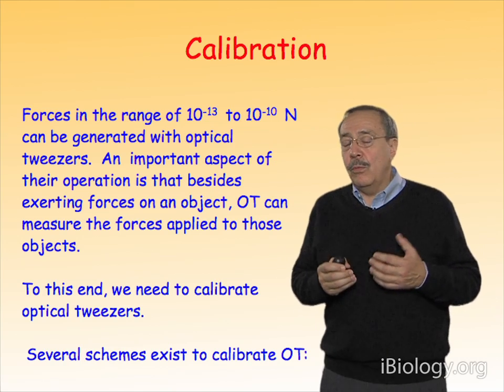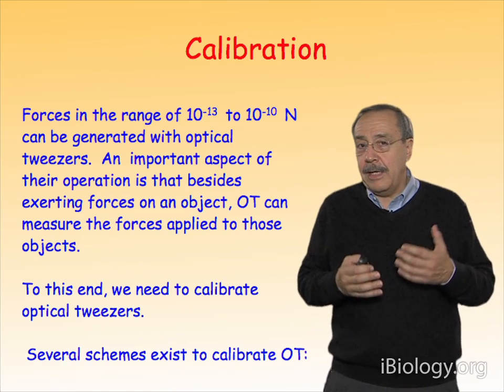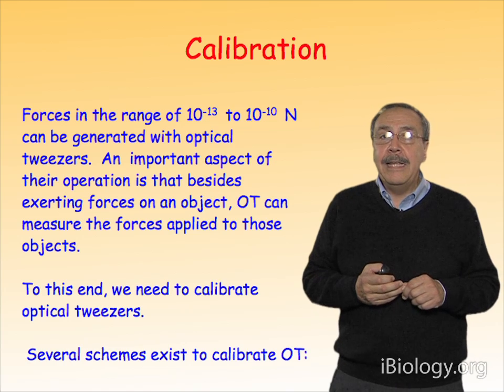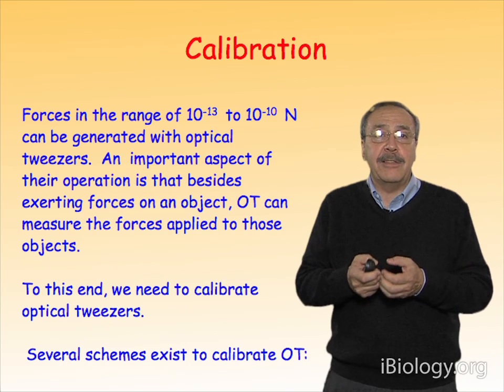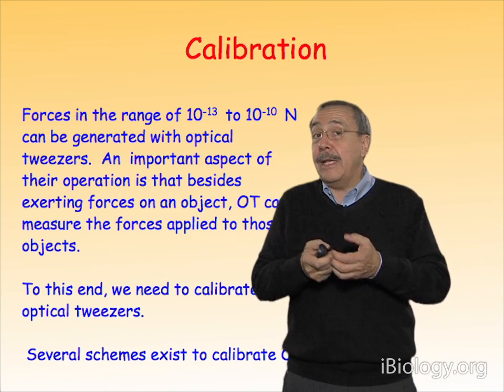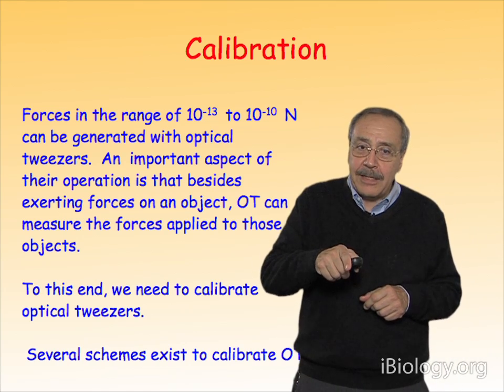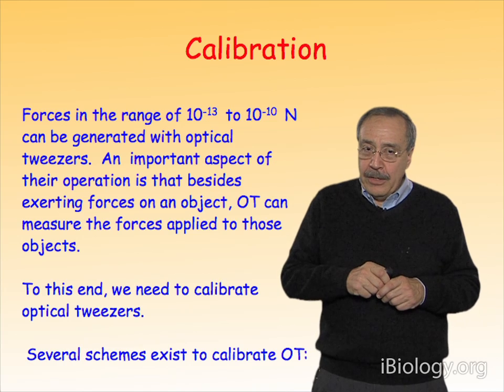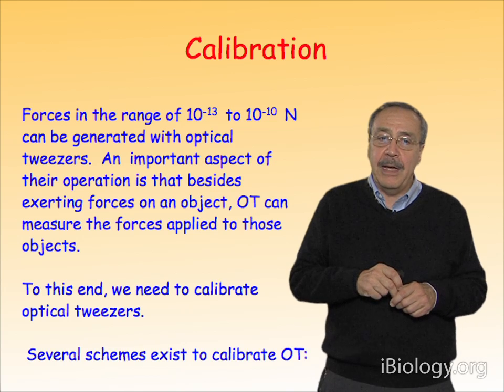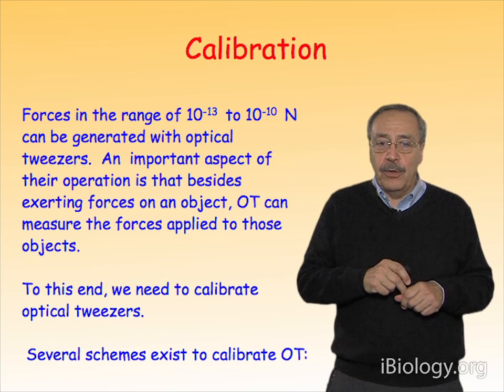One of the wonderful things about optical tweezers as a technique to manipulate and study biological processes is that they not only allow you to exert forces on molecules using the force exerted by light on matter, but they are also able to tell you how much force you are exerting on those objects. You can not only apply force, but you know how much force you are applying. For that, of course, you need to calibrate your optical tweezers.